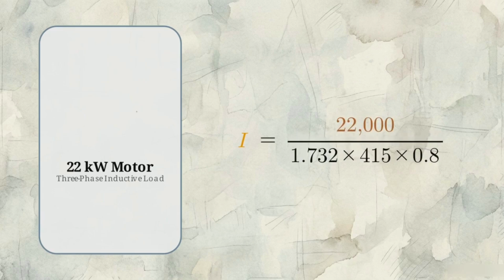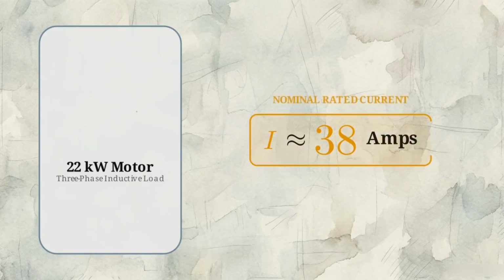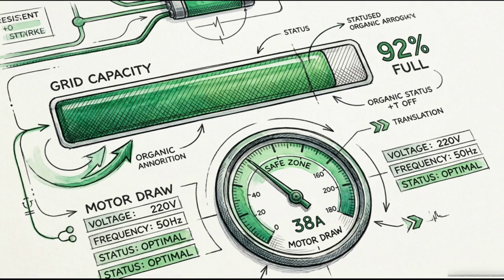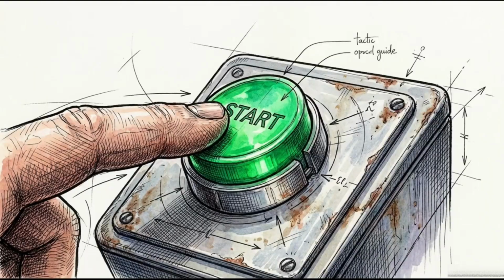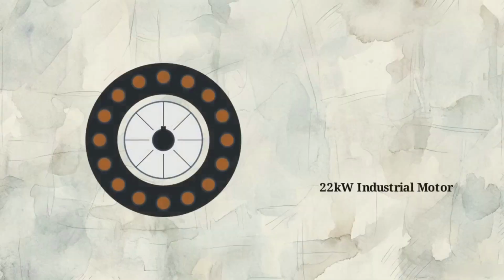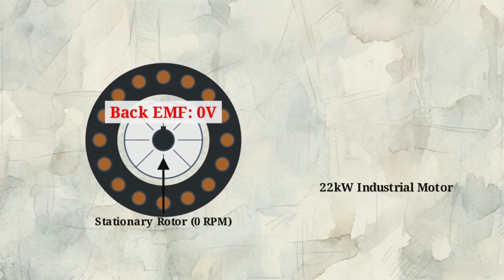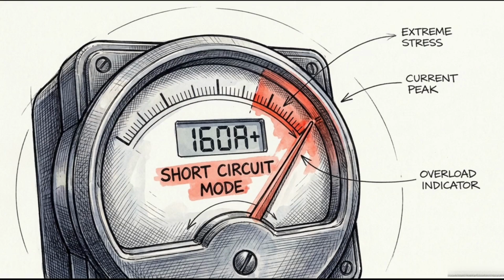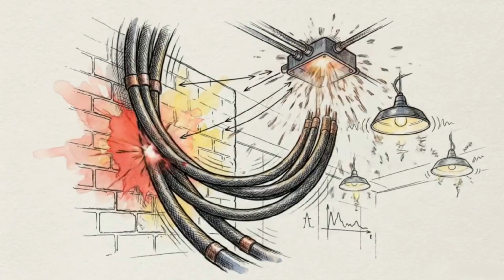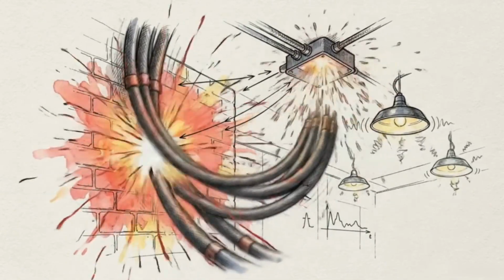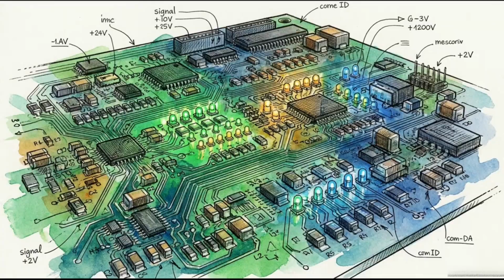To understand this surge, we calculate the motor's nominal running current using the three-phase power equation. We isolate current, dividing the 22,000 watt rating by line voltage and power factor. At full load, it requires 38 amps. If the facility is designed to handle a 38 amp draw, it seems contradictory that starting the motor would cause the entire grid to sag. The cause is the rotor's inertia. At the exact second of startup, internal components are completely stationary, meaning they aren't cutting through any magnetic flux. This stationary state means there is zero back EMF, the internal opposing voltage that restricts current. Without back EMF to resist the flow, the motor acts as a near short circuit. It violently pulls up to 6 times its rated current, spiking past 160 amps, and completely starves the rest of the facility of voltage.